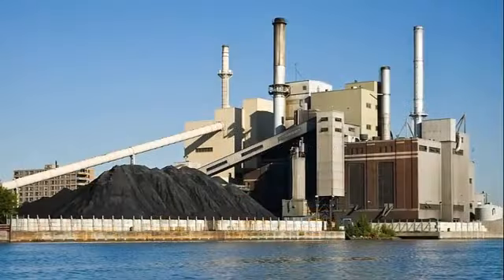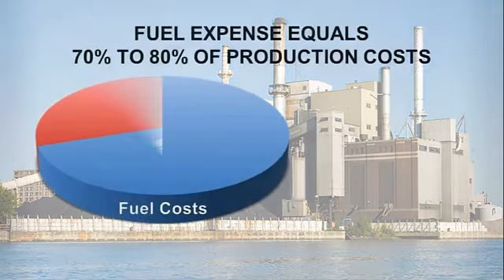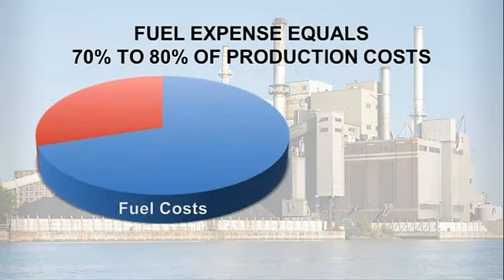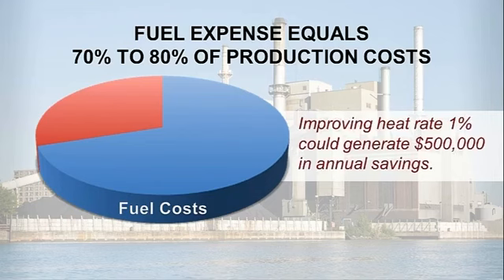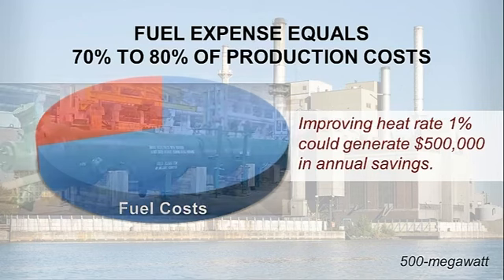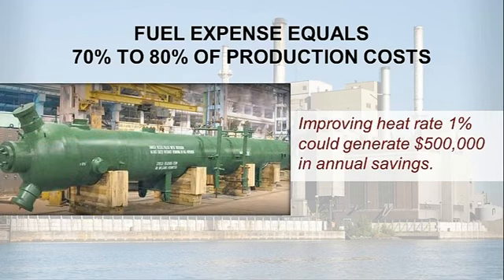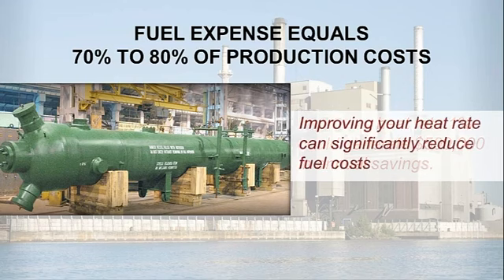For most power plant operators, fuel expenditures account for 70 to 80% of production costs and millions of dollars per year. In fact, improving heat rate 1% could generate $500,000 in annual savings for a 500 megawatt power plant. To contain fuel costs, power plants must maximize the efficiency of their feed water heaters. That's why many companies today are focusing on improving heat rate as a way to use their feed water heaters more effectively and significantly reduce their fuel costs.